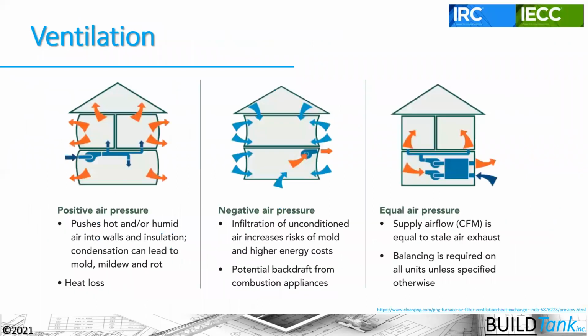There is some confusion there. The confusion comes because supply and exhaust ventilation either pressurizes or depressurizes the house, and it uses the same holes that infiltration and exfiltration uses, but it puts it on a controlled system there. So when the system isn't running, you're still getting infiltration and exfiltration, but when the ventilation system is running, you're using the same holes that air is moving through. So there's some confusion amongst building officials or even HVAC contractors about whether to double dip, in essence, on the infiltration credit and not put into that calculation the ventilation load portion of that credit.